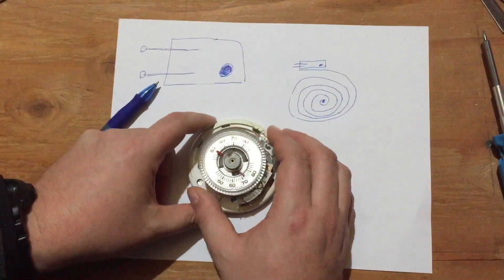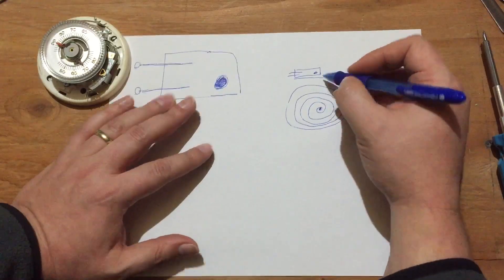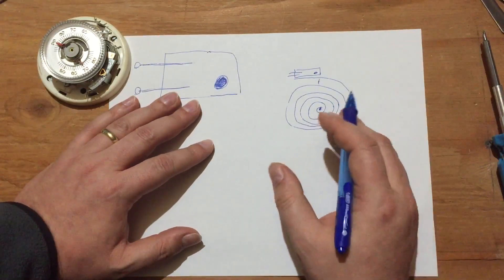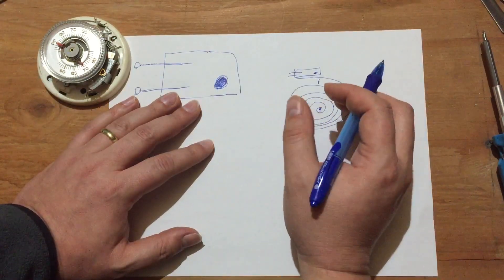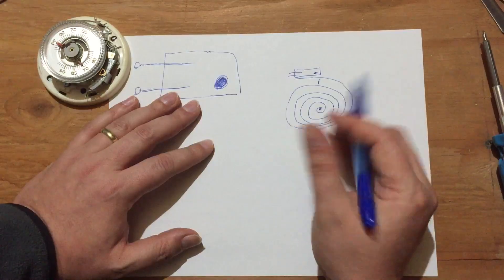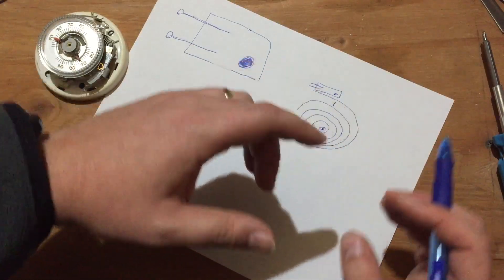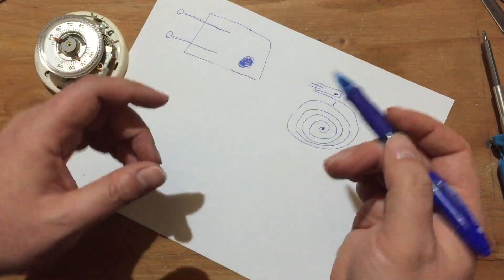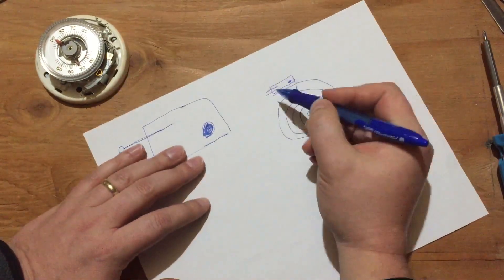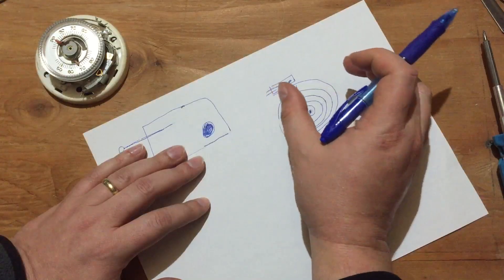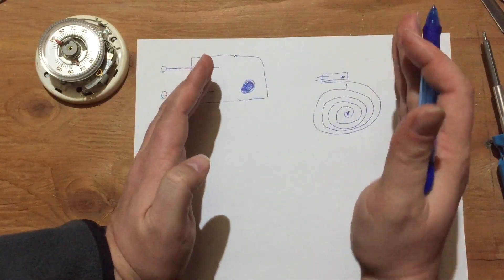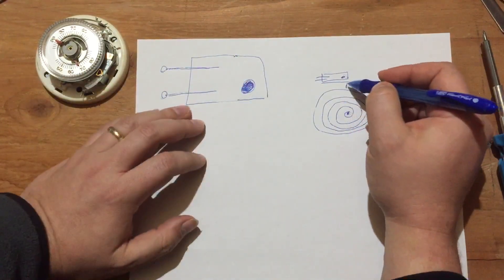So that's all that's happening. You can bring a temperature into an angle. And then, so, there will be some sort of balance point here, where some specific temperature where it has kind of the balance between on and off. And there will be a little bit of hysteresis in here where the weight of this, of the mercury ball, when it's this way, the weight of the mercury will be holding it, kind of holding it off a little bit longer. So you'll have to go extra far for it to, the ball to roll and turn it on. And then, when the ball is weighing it this way, it'll have to take a little, you'll have to heat up more for the ball to finally tilt. So it's not an exact temperature, it's sort of a, there's a lower temperature where it'll turn on and a higher temperature where it'll turn off. But there's sort of some kind of balance temperature in the middle of that.